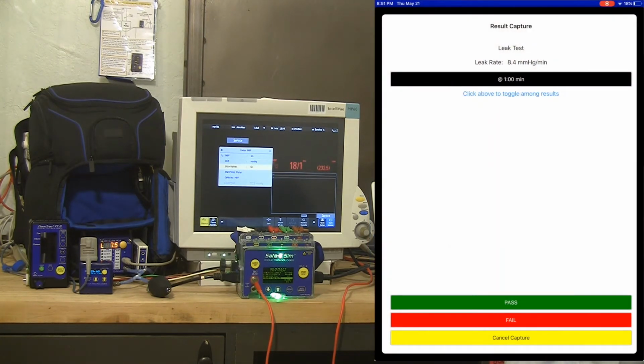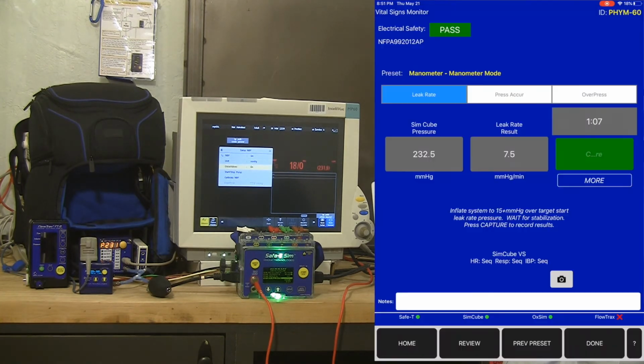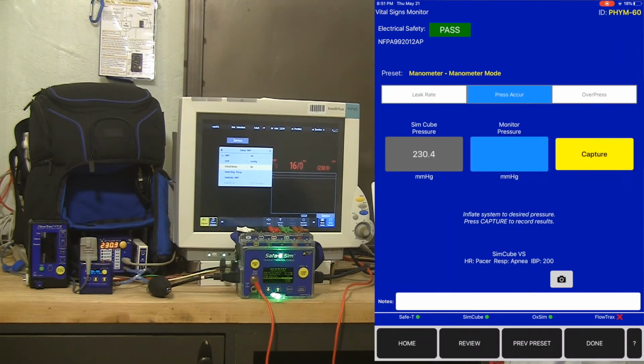You can see here that we've got a leak rate of 8.4 at 1 minute, and you can toggle that between 1 minute and 30 seconds. I'm going to call that a pass for the purpose of this. And if I need to run a second leak rate test, there's a more button directly below that pass button. So we've done a leak rate test. We can move on to pressure accuracy.